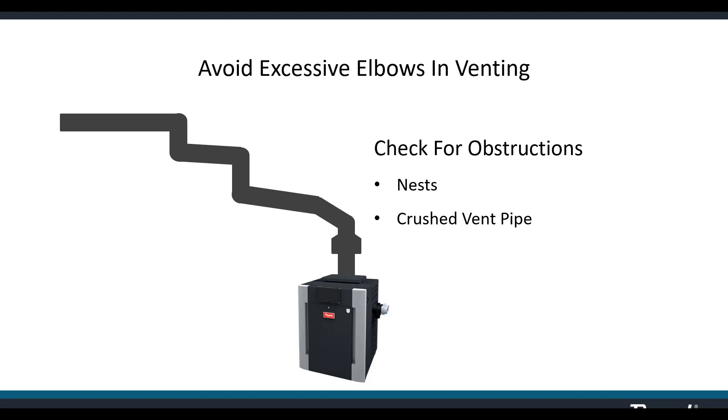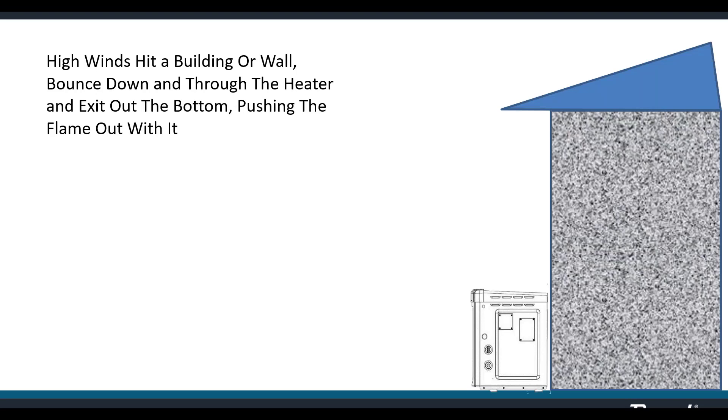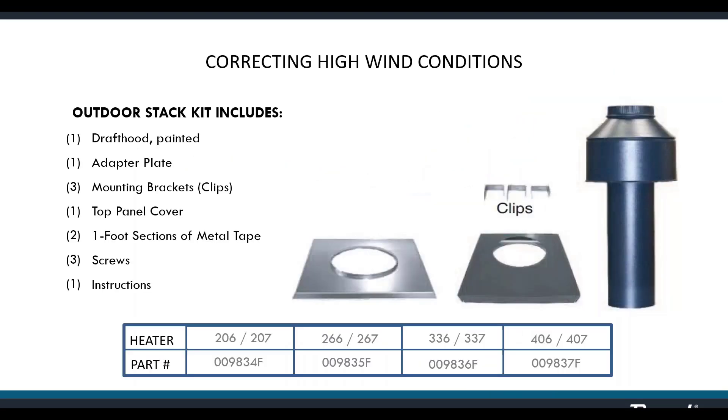Avoid stair-step elbow patterns in venting, which you sometimes find in older buildings where each subsequent installer tied venting where most convenient — this is lazy venting that needs to be corrected. High wind conditions can cause rollout: winds bounce off a nearby wall and travel downward through the top of the heater and out the bottom, pushing the flame out with them. We can fix that by installing an outdoor stack kit, which comprises a draft hood and ancillary products in four sizes corresponding to the heater sizes.